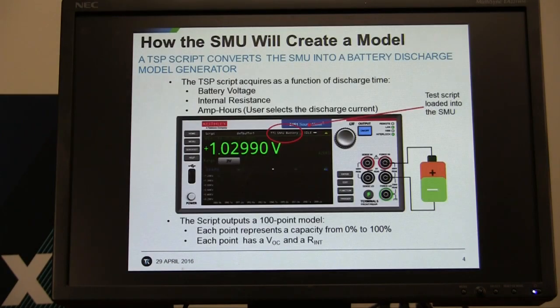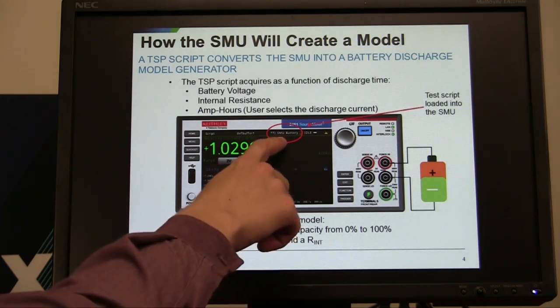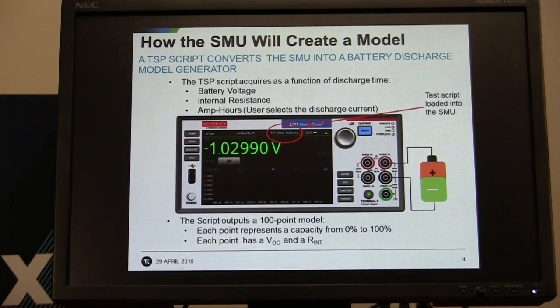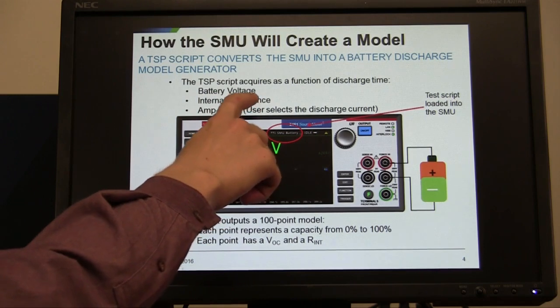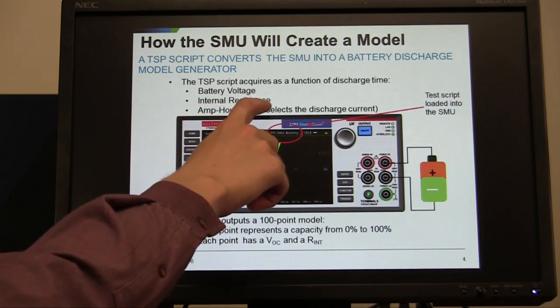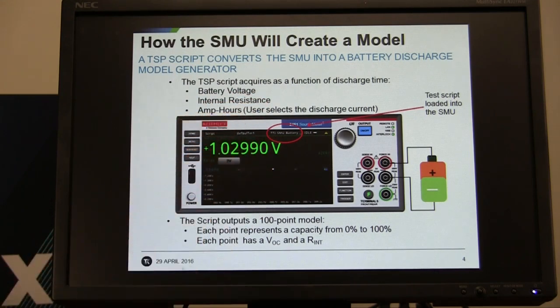So how is the SMU going to create this model? Essentially, you're going to load a TSP script from the front panel and that TSP script will run and collect battery voltage, open circuit voltage, internal resistance, and amp hour capacity data from the battery.